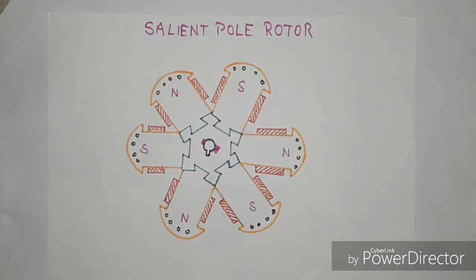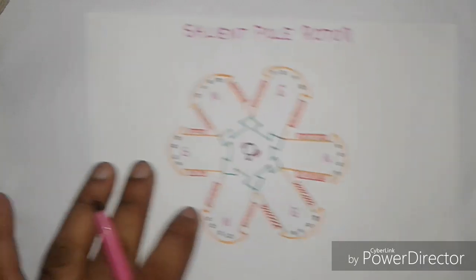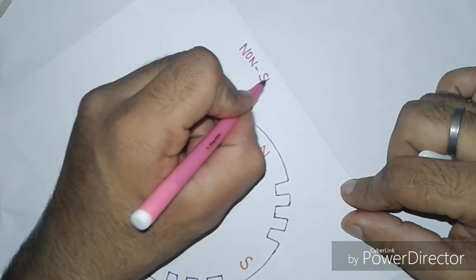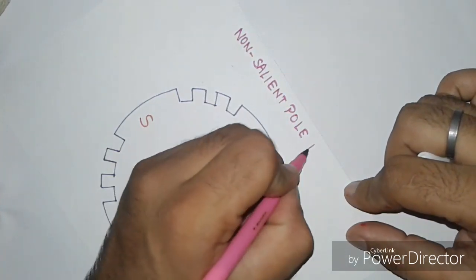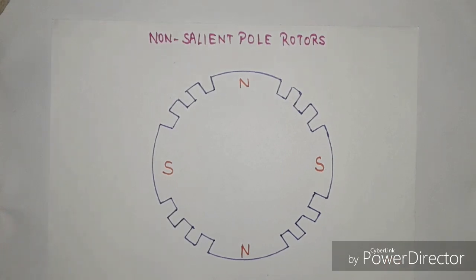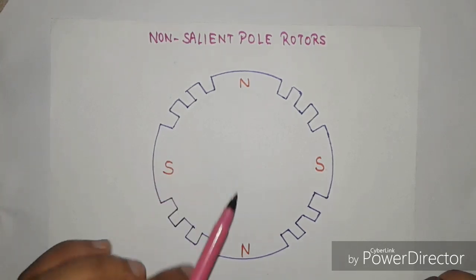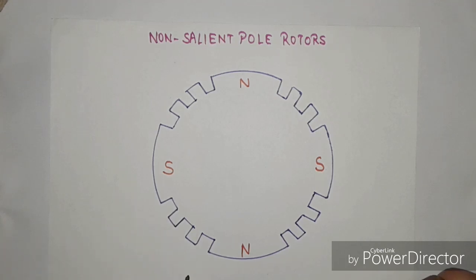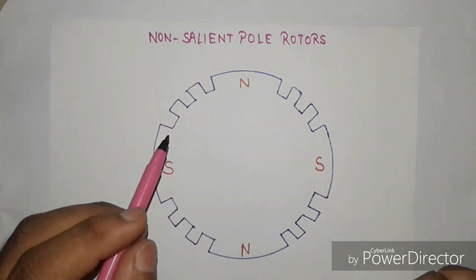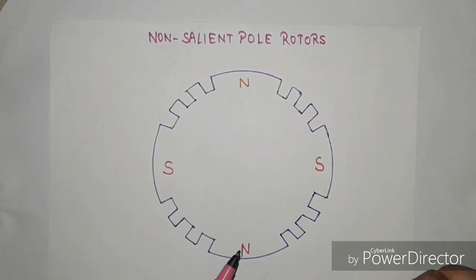The next rotor is non-salient pole type rotors. These rotors are also known as cylindrical type rotors. These rotors are used for very high speed alternators such as thermal power plants. Cylindrical rotors are made up of solid forging of high-grade nickel chrome molybdenum steel.